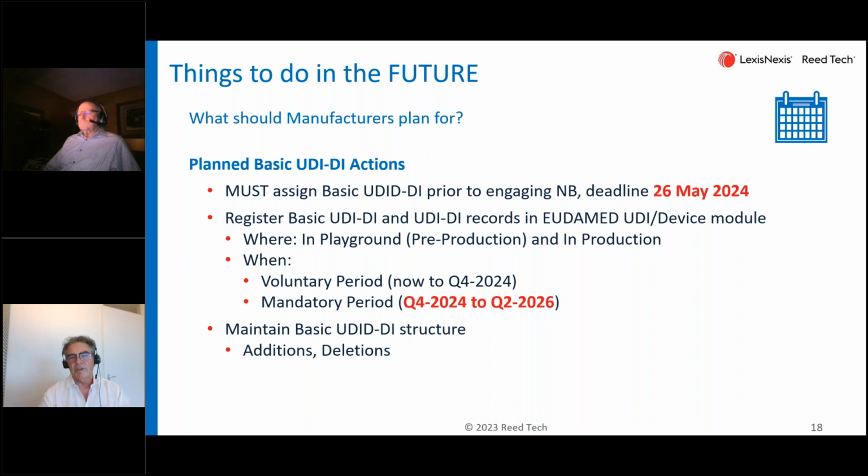That's very important. Now, if you have your basic UDI structure within your technical documentation, so you have your data set managing your devices, and things change, you have new devices entered, maybe a completely new concept, then you must keep updating that. Until you are certified under the MDR or IVDR, I suggest you already use this basic UDI concept to organize everything and to identify internally. At the moment you're certified, you have to go outside and identify externally.